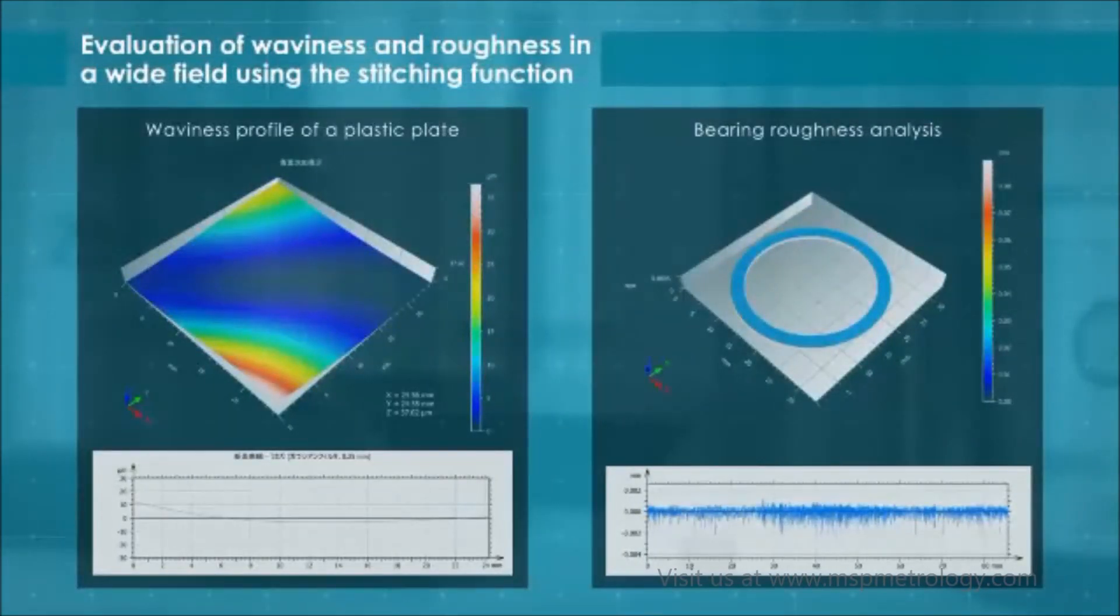This is the evaluation of waviness and roughness in a wide range. The stitching function enables you to conduct evaluation beyond the measurement range of the interference lens.